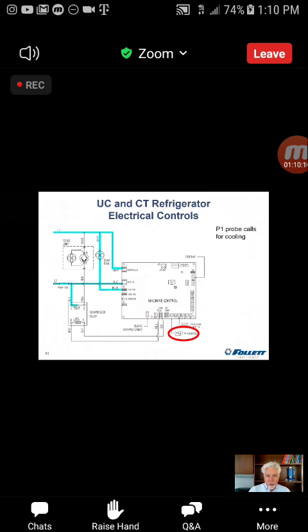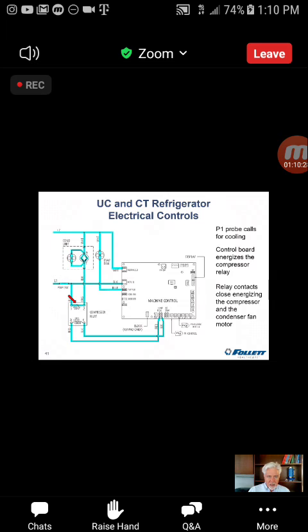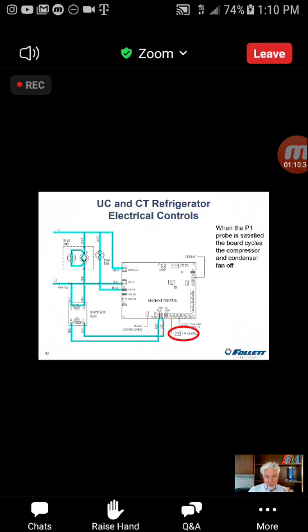So when we're calling for cooling, and again, that's based on the P1 probe, that's the one on that return air grill on the rear panel inside the cabinet, then the board is going to send 24 volts DC, okay, over to the compressor relay. And then we close the contacts and we energize the compressor and the condenser fan motor. As we mentioned, they're polarity sensitive, so just be aware of that. If they're switched, it doesn't damage anything, but the compressor won't do anything because the relay is not going to send any power to it.